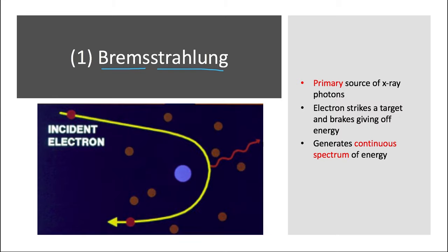So together it means breaking radiation or deceleration radiation. So bremsstrahlung is the principal source of x-ray photons. The high energy incident electrons are attracted to the positive nuclei of the tungsten and strike the target as a result. But this results in the deceleration or breaking of that electron where their loss of kinetic energy is converted into x-rays. So this generates a continuous spectrum of energy.